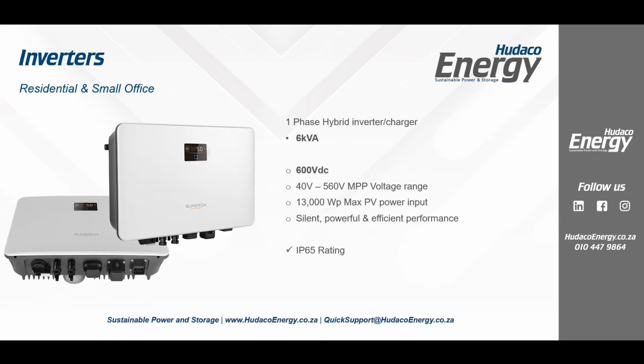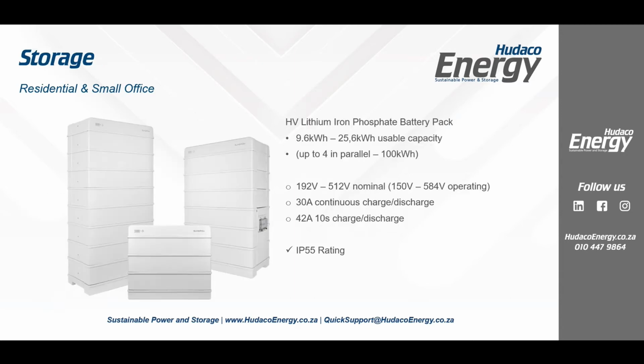Okay, so this here is the inverter. The batteries look like this. At the bottom, you've got the base. Now, the base comes either with foot pads or with screw-in feet, if you want to raise it a little bit off the floor, for example, if it's on a concrete garage floor. The top section is your battery management system, which comes on the top, and that closes the circuit. And then in the side, you've got your protection, right? So this is your communications and your protection box. And on the top of here, you've got your SunClix connectors for your positive and your negative cables, your communications cable, which also gets supplied in the box with an RJ45 connector piece, and your earth bonding point. They then go up the back of the top, and you connect to your inverter.